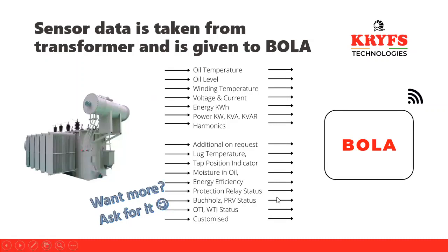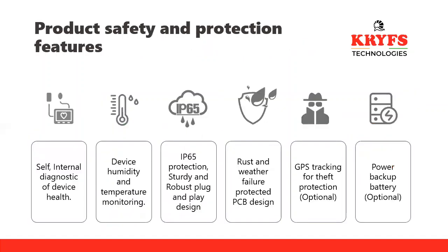If we talk about which parameters can be covered, normally we can cover any and all parameters of the transformer, but just to mention, we have oil temperature, oil level, winding temperature, voltage and current, energy, power, harmonics, etc. Additionally, we can have lug temperature monitoring, tap position indicator, moisture in oil, energy efficiency, protection relay status, Buchholz PRV status, OTI, WTI, and any other customized parameter. We can even offer control of the cooling fan, control of the cooling pump motor, or any other control function which may be required. Local annunciation, etc. is also available. If you want anything else, we can definitely integrate that.